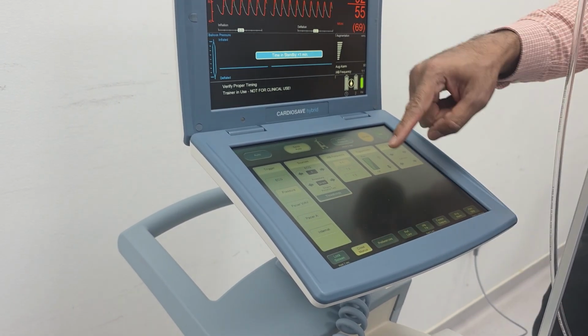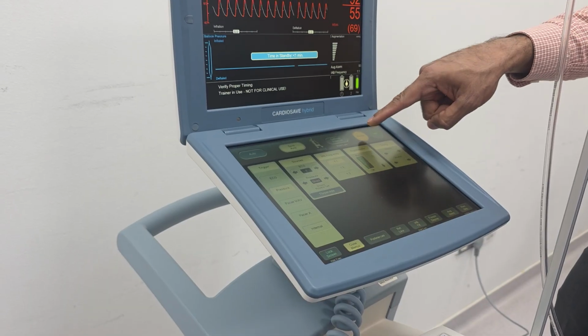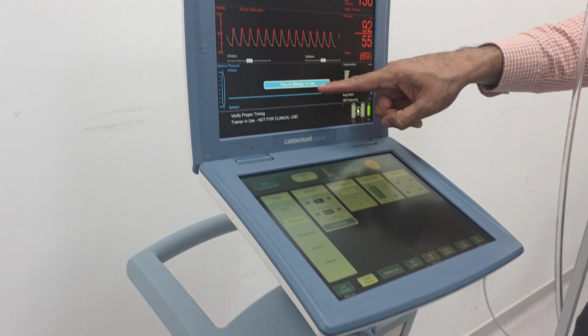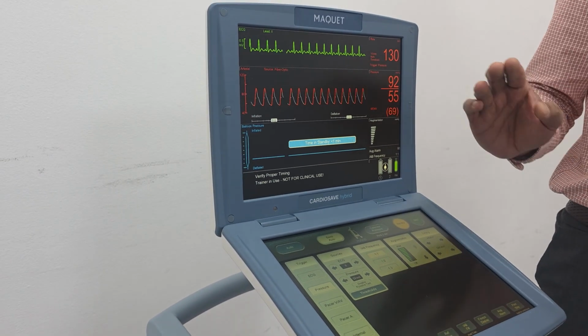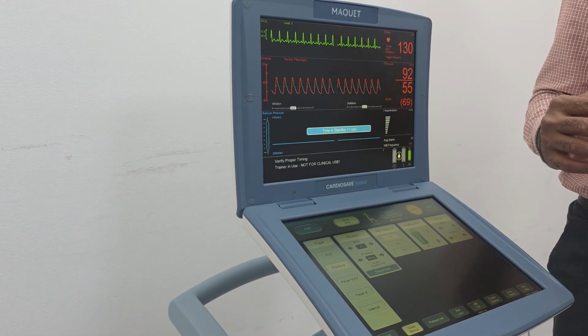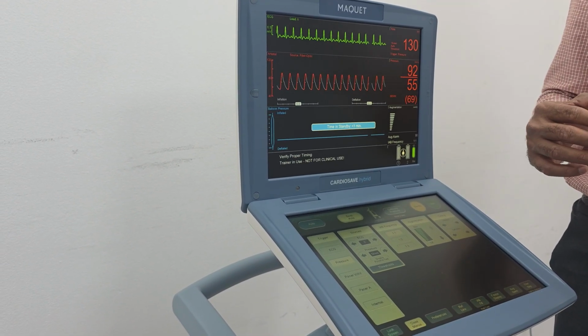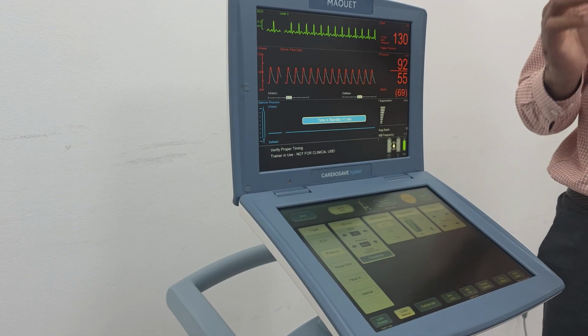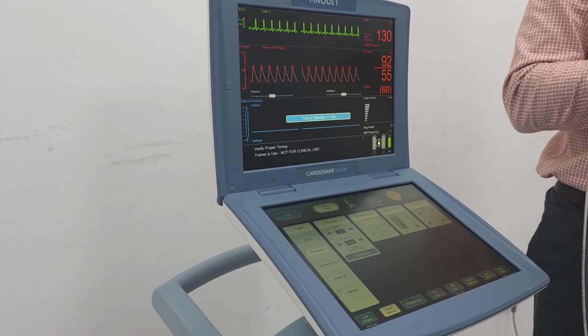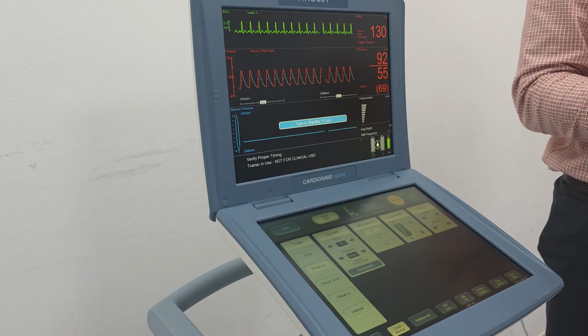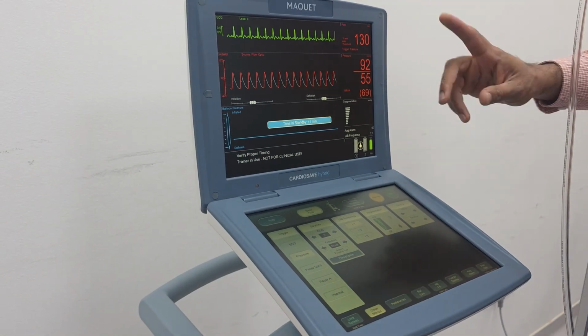Okay, so now the machine is in standby mode. See, time in standby less than 1, same like CS300. When it reaches 10 minutes, it will give you a low priority alarm. When it's about to reach 30 minutes, there should be a continuous alarm, because we are not recommending to keep the balloon without inflation more than 30 minutes because of the thrombus formation. Okay, so we can start pumping.